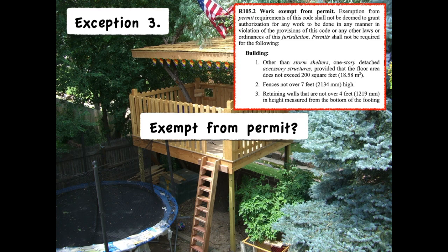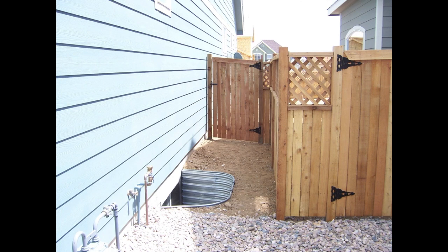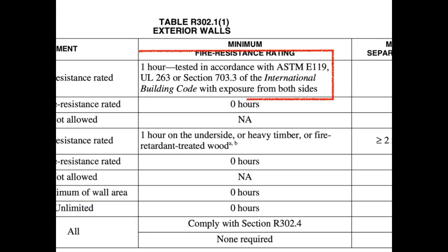The IRC allows structures up to 200 square feet with no permit. When fire separation distance does apply, if the face of the wall has a 5-foot or greater fire separation distance, then no protection whatsoever is required. But if it's less than 5 feet, then it must be provided a 1-hour fire resistance rated wall with exposure from both sides, protecting a fire in either direction.